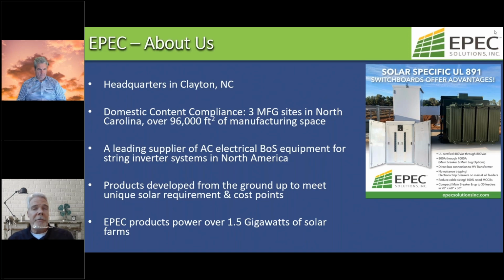Over the last 7 years, we have become a leading supplier of electrical balance of system equipment for string inverter systems. If you look on the right, one of our industry magazine ads is for solar specific UL891 switchboards. From the beginning, which was in 2018, we worked very closely with UL to develop a UL891 switchboard that met the criteria for 891, but also met the criteria for solar. We really developed that from the ground up for solar, and we think for that reason the product has really taken off, just because we planned to meet the specific needs of solar from the beginning. To date, we power a little over 1.5 gigawatts of solar with the switchboards that you see on the right there, and you'll see a little bit more as we move forward. Next slide.